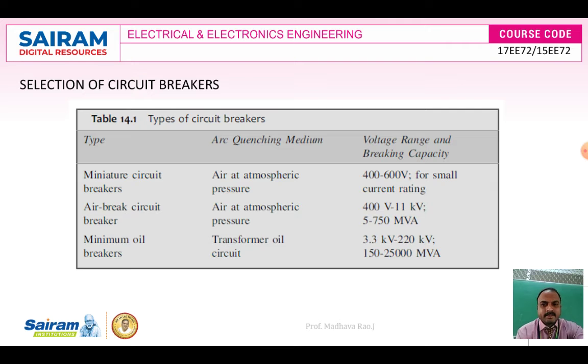So we can see the selection of circuit breakers here. The parameter we use to select circuit breakers is voltage. Here, the miniature circuit breaker, MCB: air at atmospheric pressure, used for 400 to 600 volts. The air break circuit breaker: air at atmospheric pressure, 400 volts to 11 kilovolts. The minimum oil circuit breaker: transformer oil, 3.3 kilovolts to 220 kilovolts.